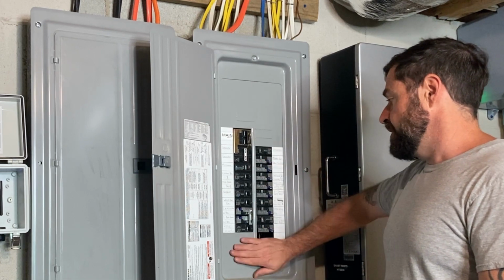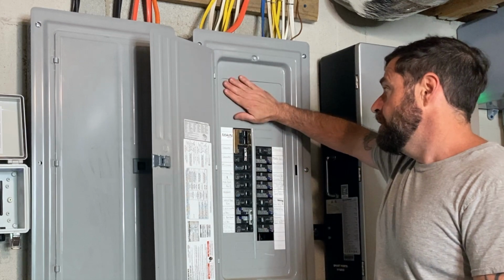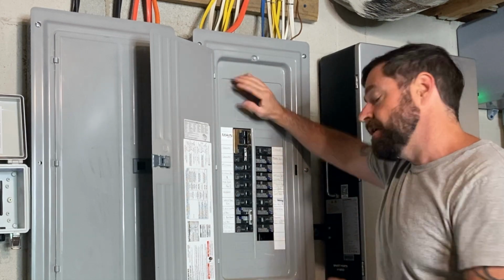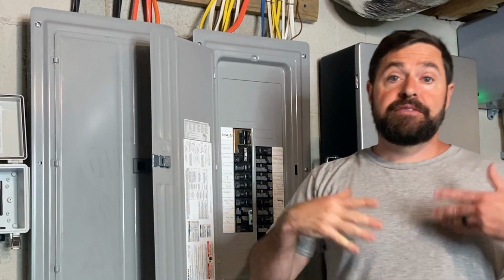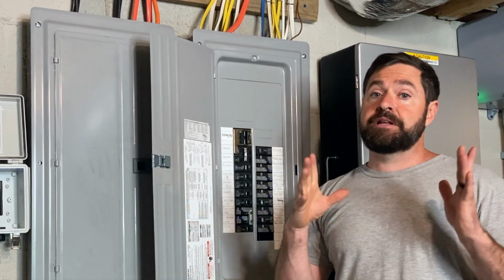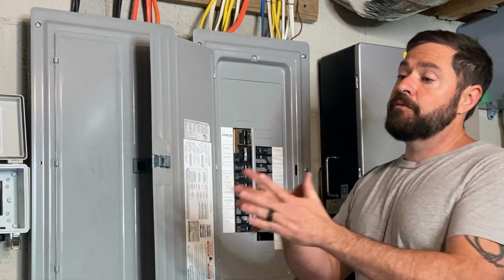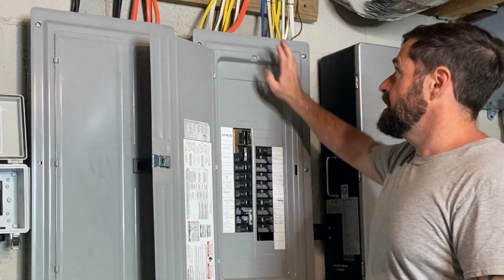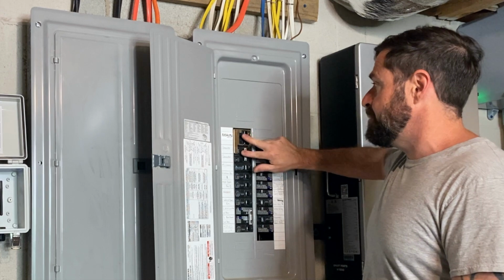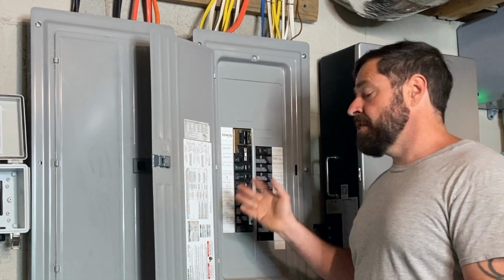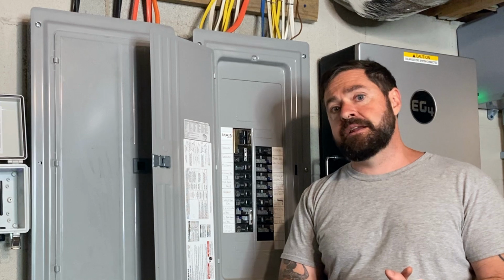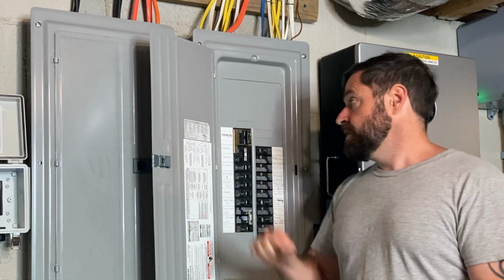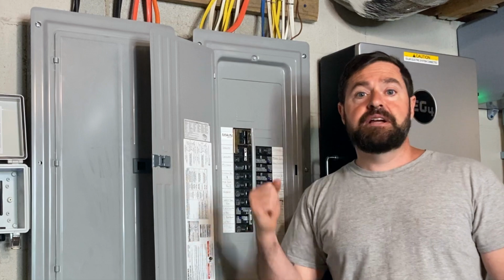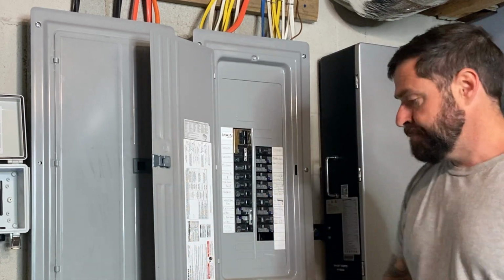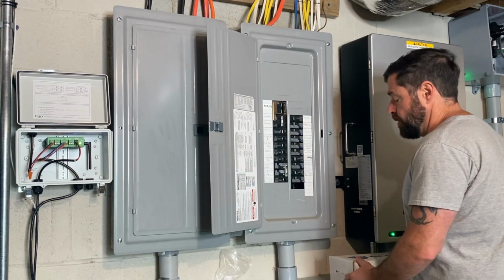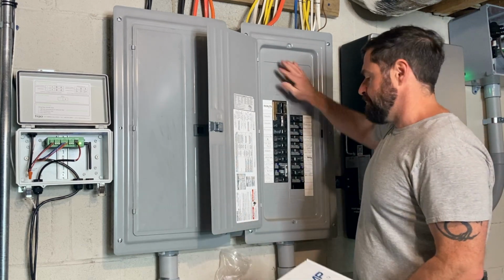Really, I want to protect this panel from surges and from dirty power. Now I am going to be hooking up the EG4 Chargeverter, converting that generator over to charging my battery bank. But I am probably going to leave this generator interlock kit in place as another form of redundancy, so that worst case scenario, I can disconnect this panel from everything else and run it on a standby generator. So I was pricing out whole home surge arresters for my backup panel here.